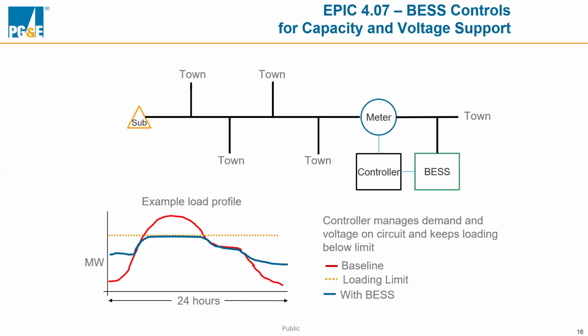On the previous slide I showed the distance for scale. The battery is about 40 miles electrically away from the substation. For distribution, that's a far distance; for transmission, that's not really any distance, but at the distribution level it's very far. We're providing electric service to numerous towns along the way, and to allow more capacity, the battery is located near the end of the line so that capacity can be freed up all the way up to the substation.